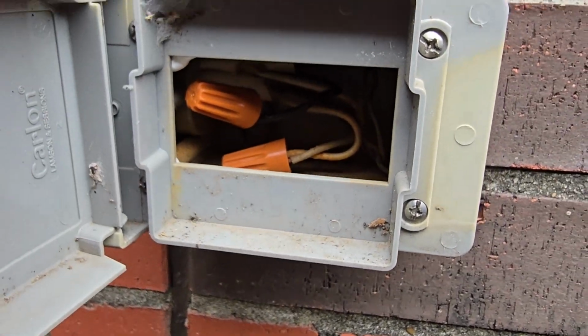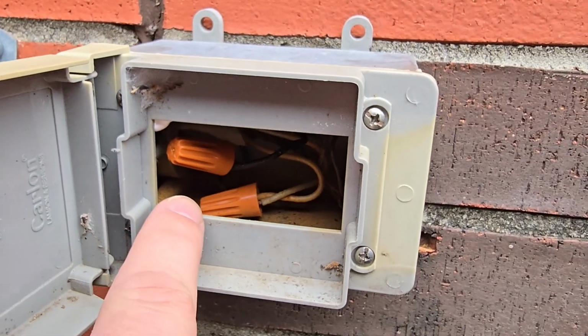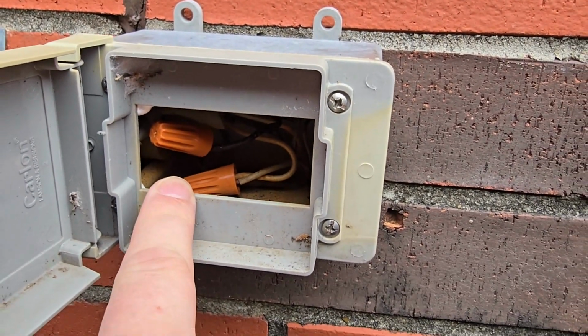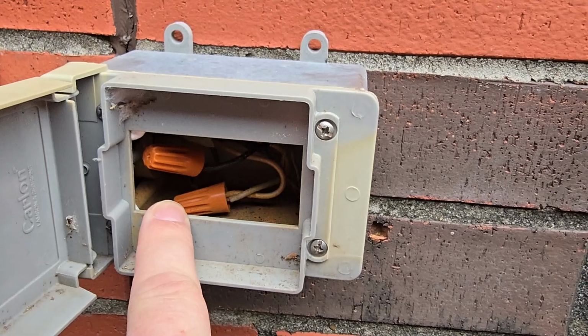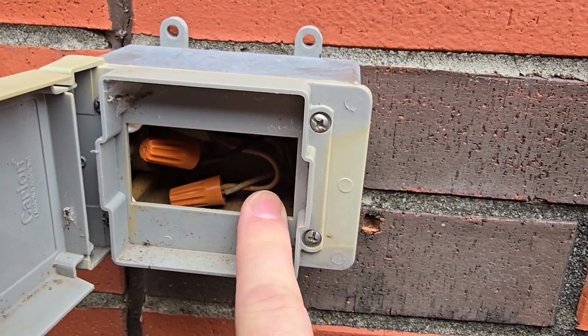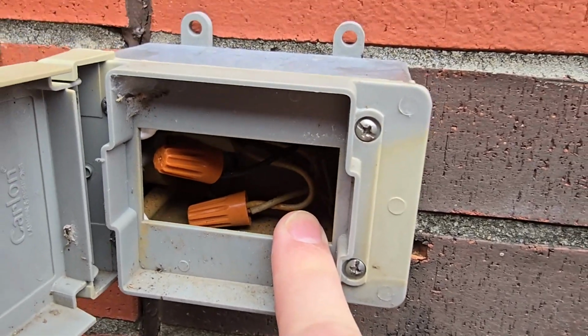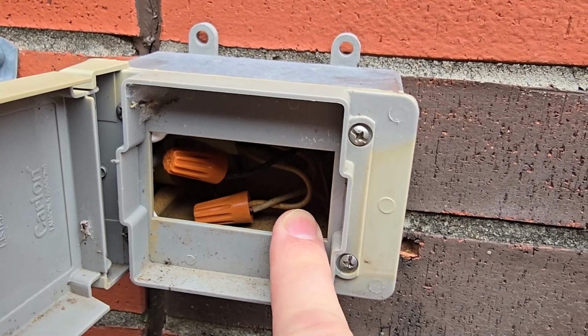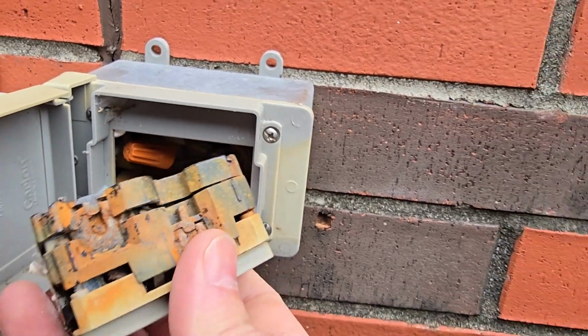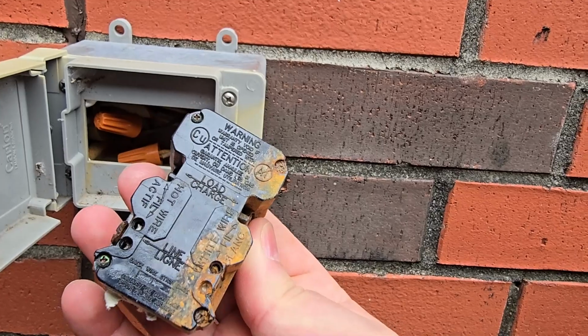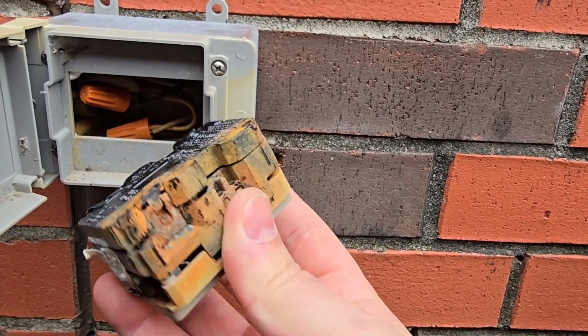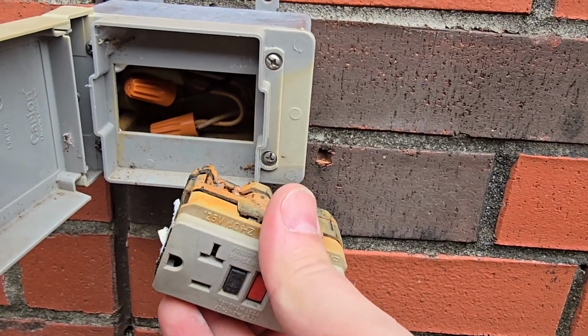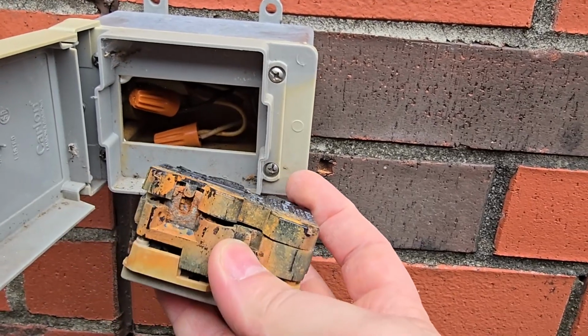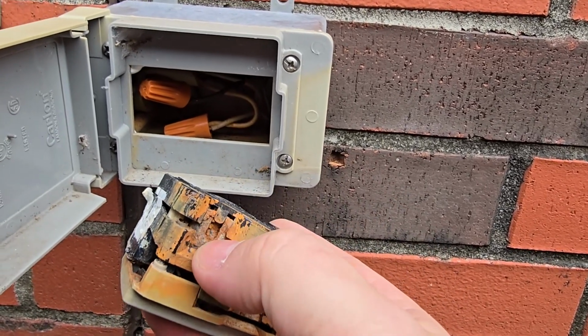What I couldn't make out is I have a hot and neutral coming in, clearly 120 volts across them, and then a hot and neutral going out. All of those were in a really bad condition, and some weren't even connected. The hot line was not connected to this one, it had just snapped right off due to the fastener disintegrating. You can see right there.